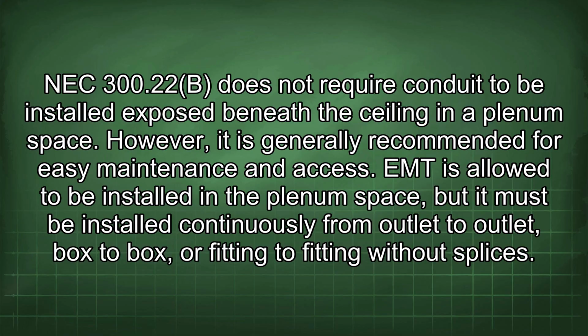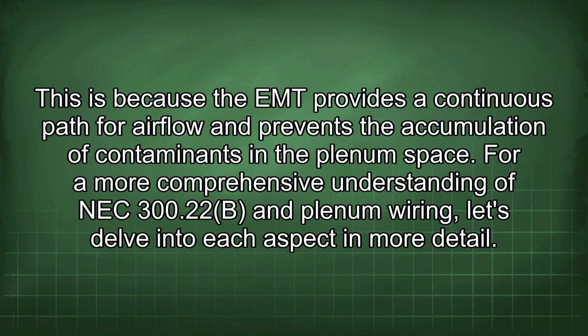EMT is allowed to be installed in the plenum space, but it must be installed continuously from outlet to outlet, box to box, or fitting to fitting without splices. This is because the EMT provides a continuous path for airflow and prevents the accumulation of contaminants in the plenum space. For a more comprehensive understanding of NEC 300.22(B) and plenum wiring, let's delve into each aspect in more detail.